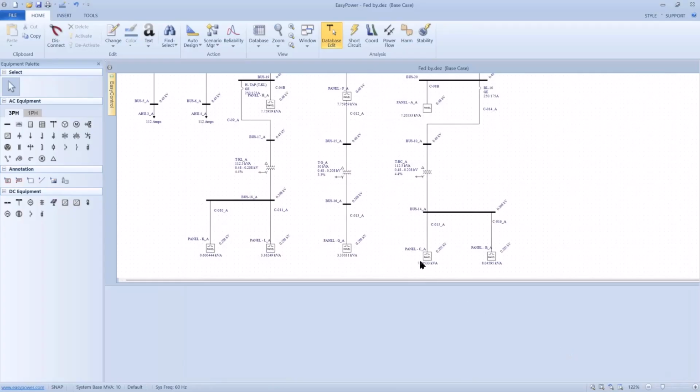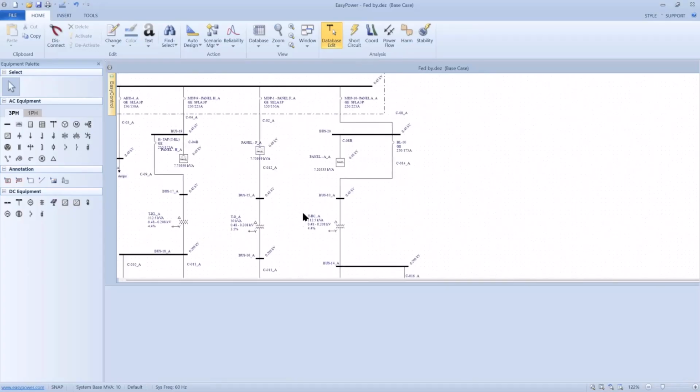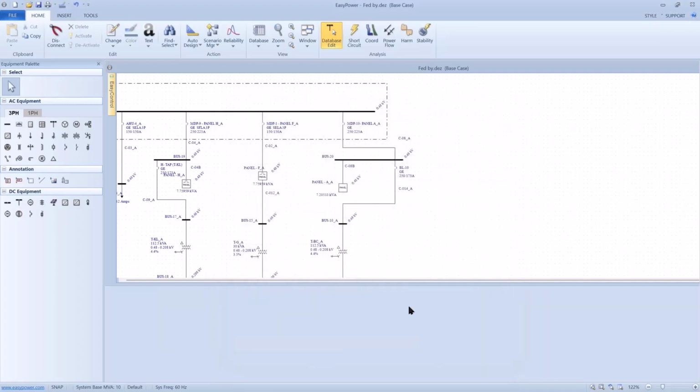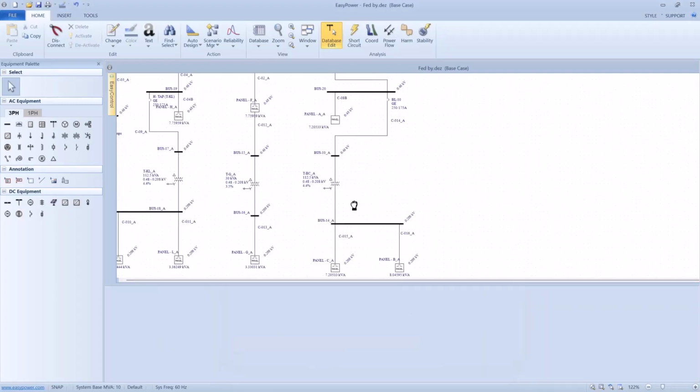The problem here is the voltage is lower when we go through a transformer and do arc flash calculations. So there's going to be a max current limit no matter what, if I'm going through a system with primary protection only.